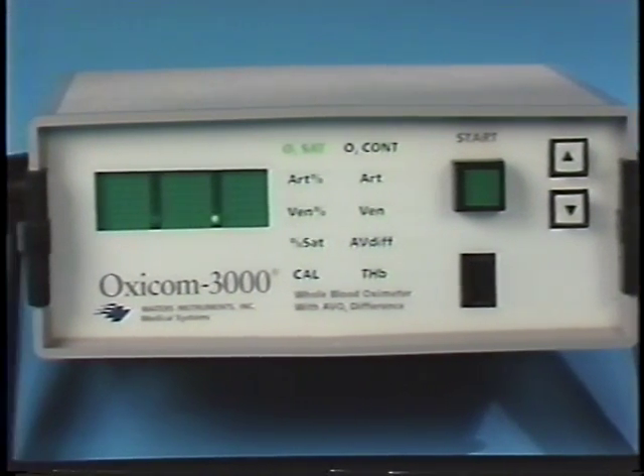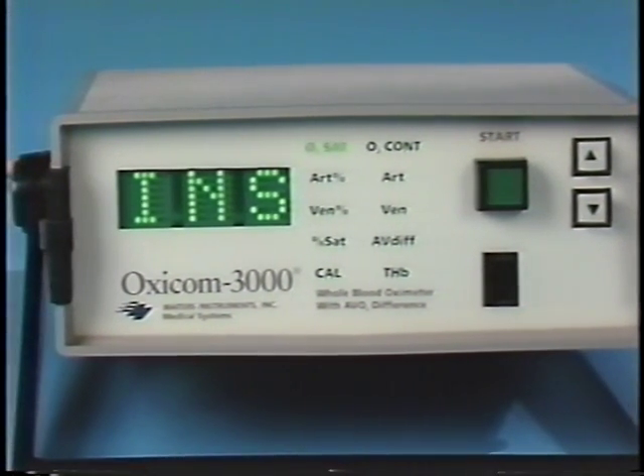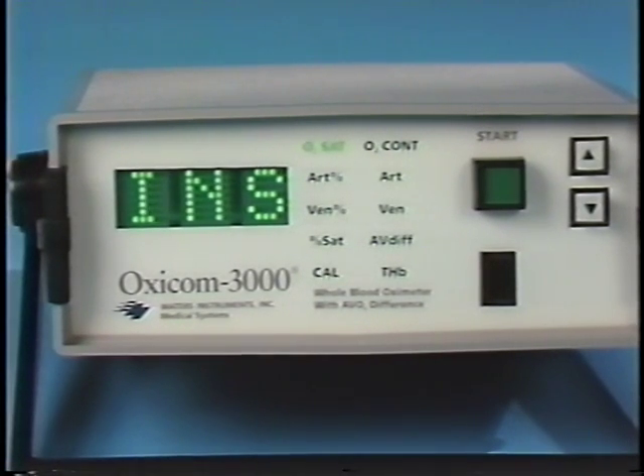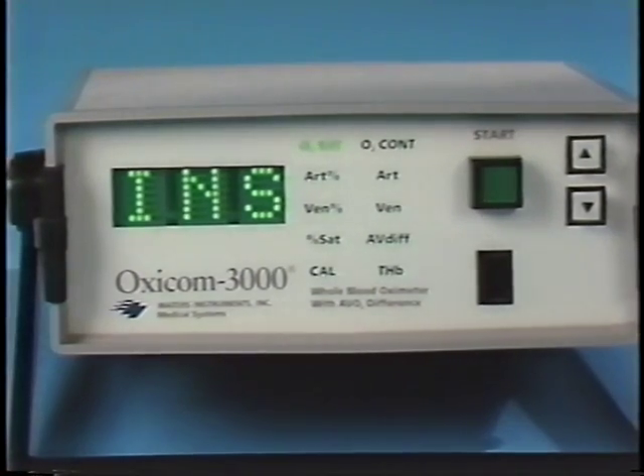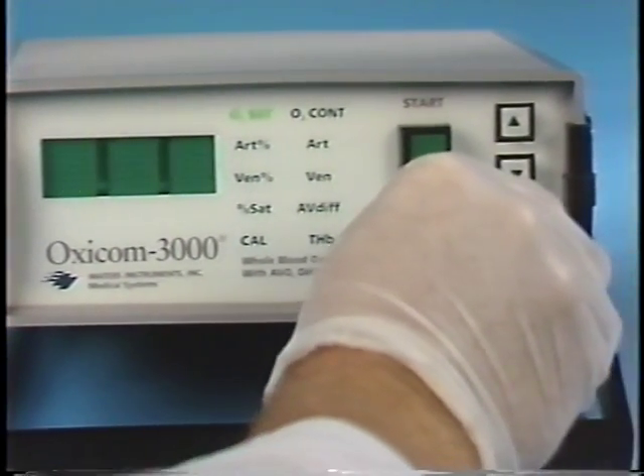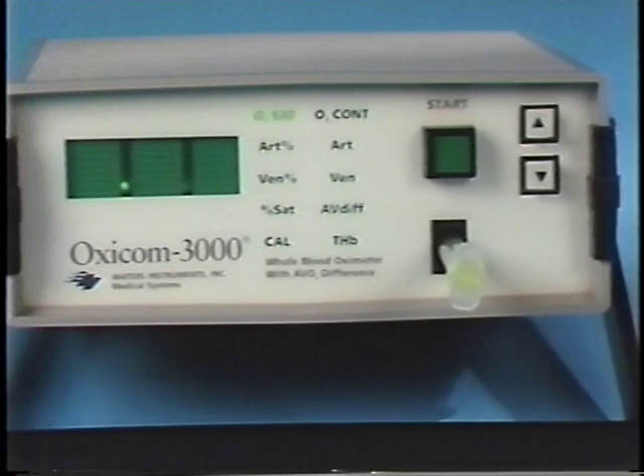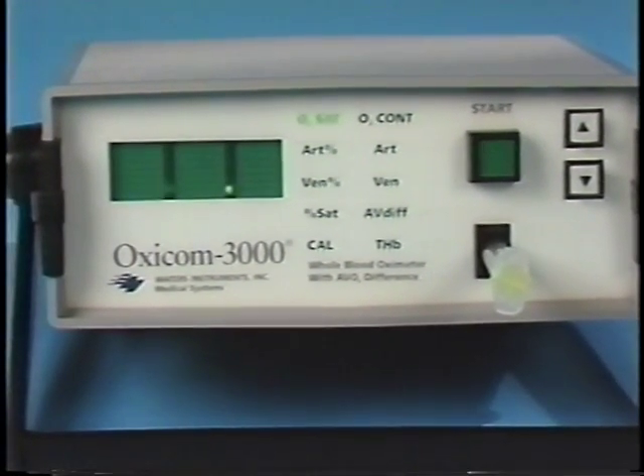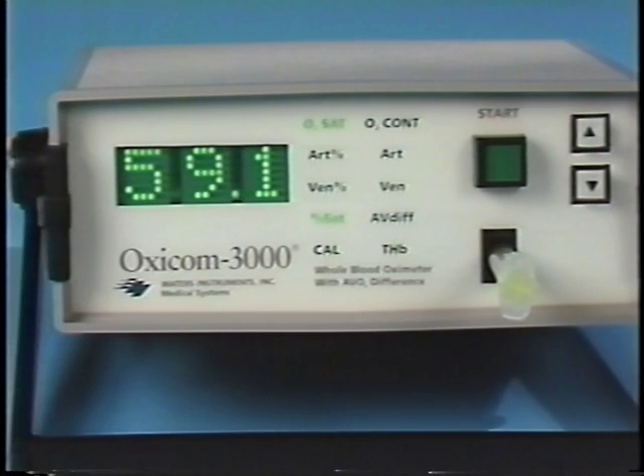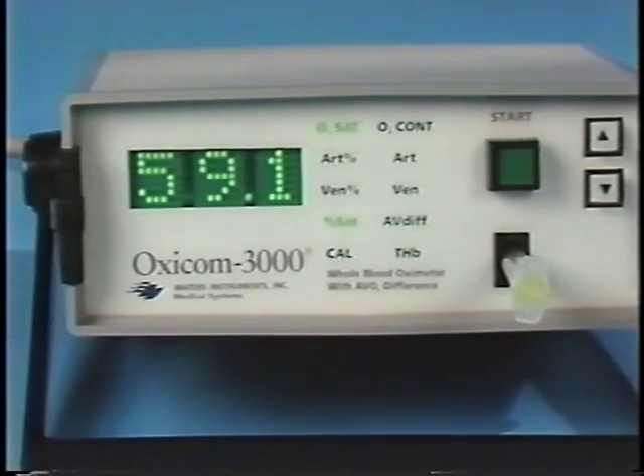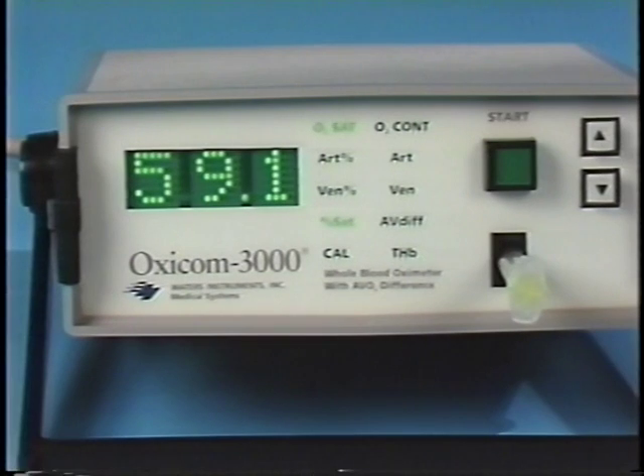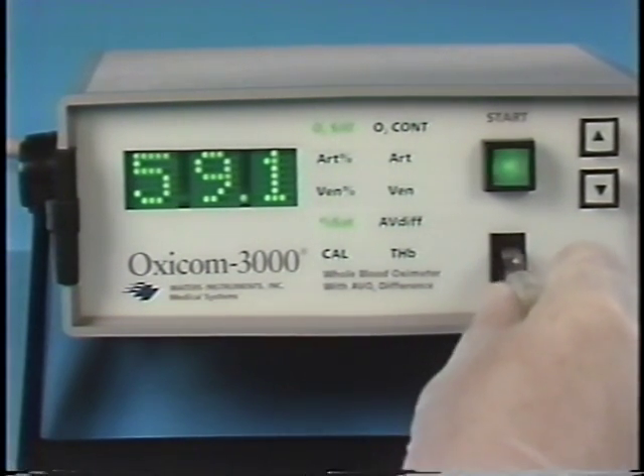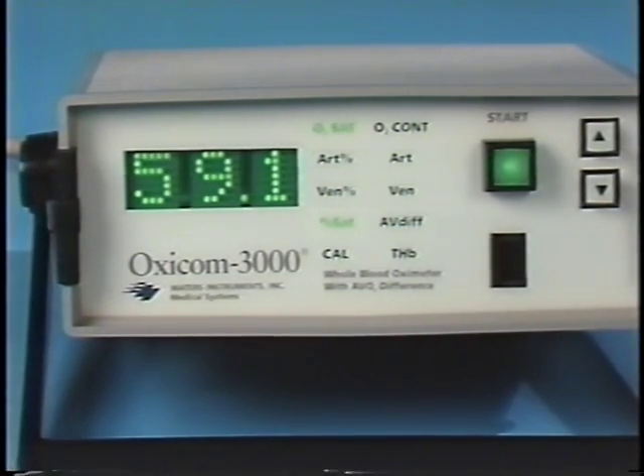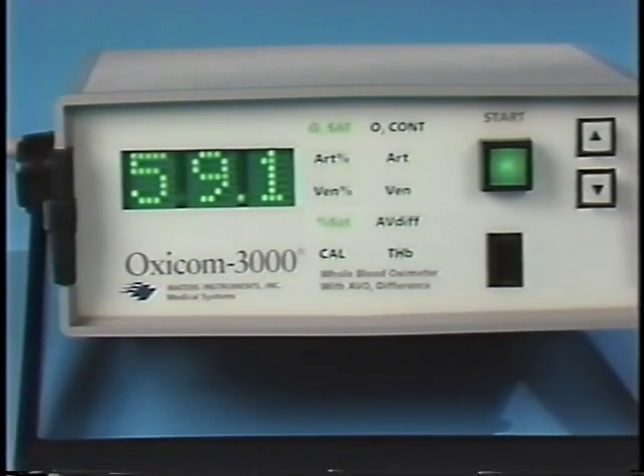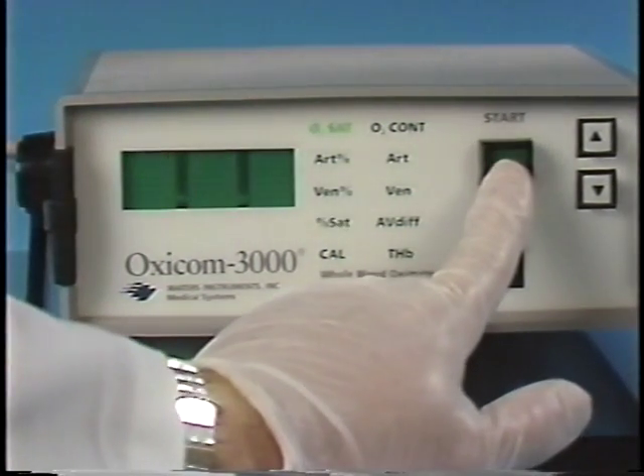The oximeter is now balancing on room air. After 6 to 7 seconds, INS for insert appears. Insert the cuvette into the sample chamber. In less than 10 seconds, the display will show the measured oxygen saturation. To measure subsequent samples, remove the cuvette from the sample chamber. The green start button will again light, and the unit is ready to measure the next sample.